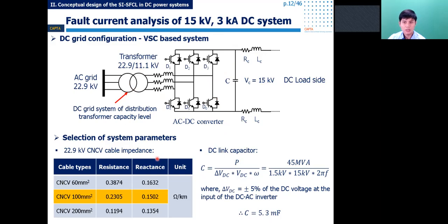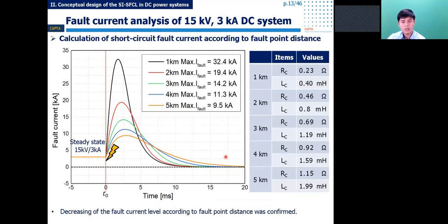The basic system parameters, like the cable impedance and the DC link capacitor of this DC system, were already determined. Also, the fault current characteristics of this DC system were simulated and analyzed. This graph shows the fault current level according to the fault distance point. In the result, you can see that the longer the distance, the lower the fault current level achieved.